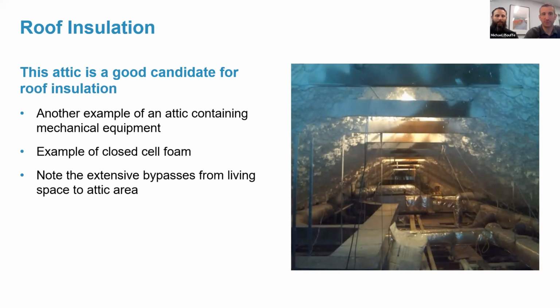As I mentioned, we're talking about a facility that might have a drop ceiling with no effective air barrier. We would call that a bypass. A bypass would be where air can freely move between the conditioned space and unconditioned space, and which can be very costly.